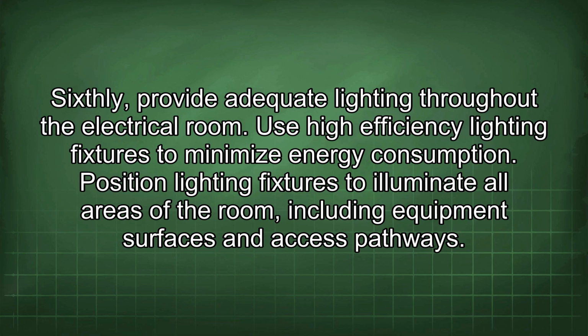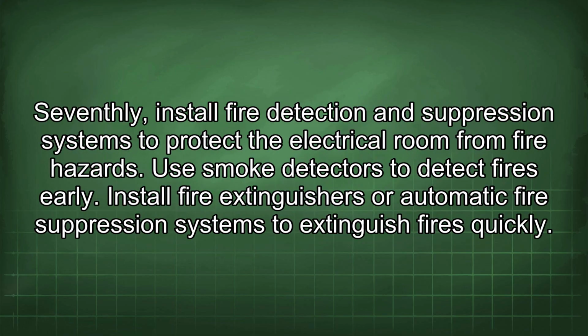Sixthly, provide adequate lighting throughout the electrical room. Use high-efficiency lighting fixtures to minimize energy consumption. Position lighting fixtures to illuminate all areas of the room, including equipment surfaces and access pathways. Seventhly, install fire detection and suppression systems to protect the electrical room from fire hazards. Use smoke detectors to detect fires early. Install fire extinguishers or automatic fire suppression systems to extinguish fires quickly.